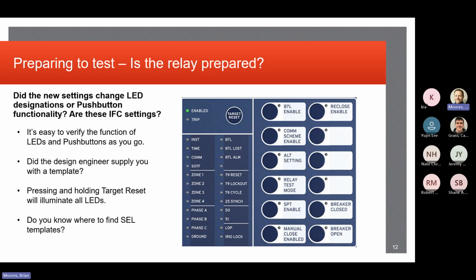So in a fault analysis, if it came to an actual analysis need, yeah, I could interrogate other adjacent, we'll call them system relays. If I have a line fault on one line and I also want to get the SER data from an adjacent line that didn't trip, I can log in and get that data, and I'm probably going to see some disturbances or abnormal conditions, even though that relay didn't trip. You can use that as a tool to help evaluate and determine things if you have to study and analyze a fault. They aren't going to communicate with each other. They're not going to send each other fault information or SER information. But a lot of times, any relay that's connected to your system, especially the close ones, might see some of those system conditions. They're just not programmed to trip for those specific conditions because that's not the element they're protecting. But yeah, you can use the other SERs, and you may need to.